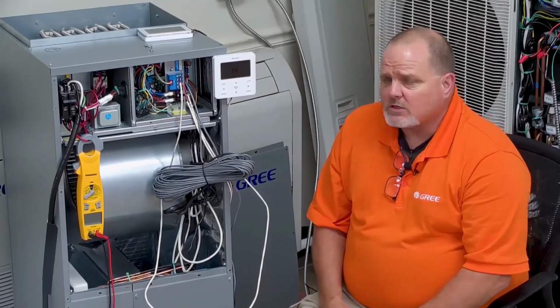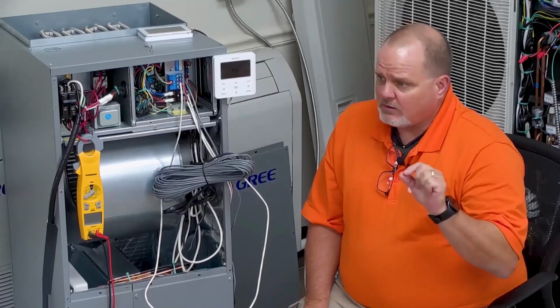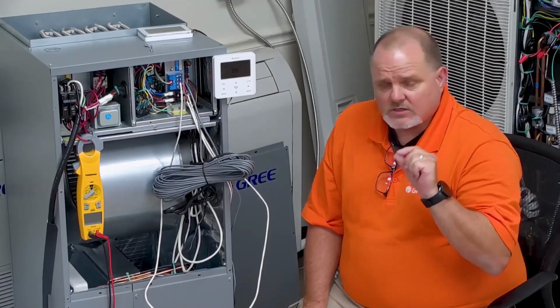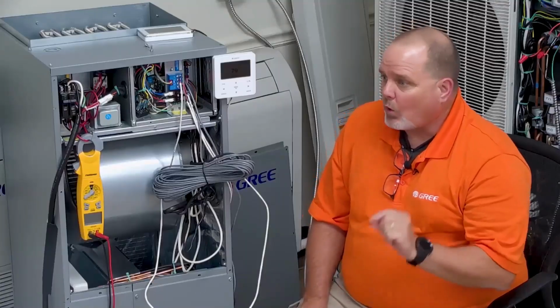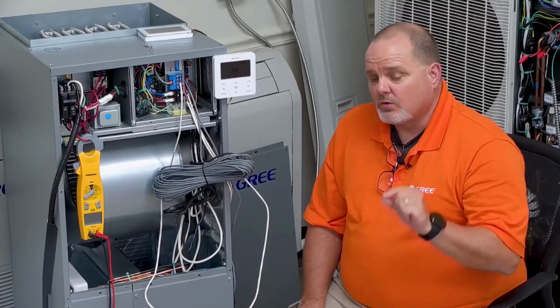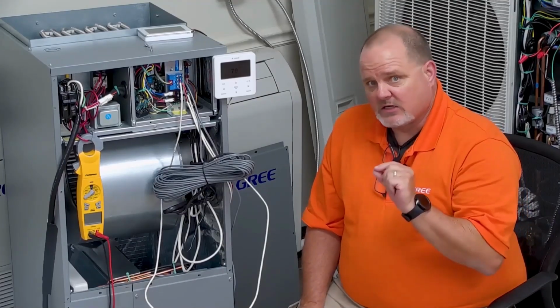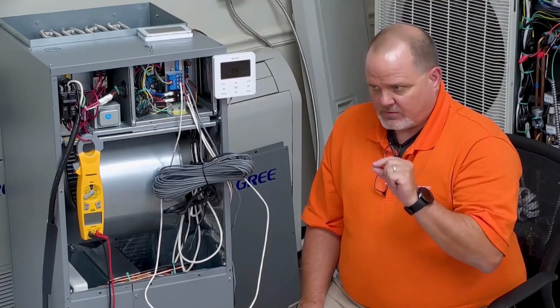With this controller, we have the ability to set it up in two different ways. You can set it up to where it will finish the heat call with the auxiliary heat. Once the auxiliary heat calls for, it will finish the call. In other words, it will not shut off the electric heat until the thermostat is completely satisfied. Or you can set it up to where it does not satisfy the thermostat completely.